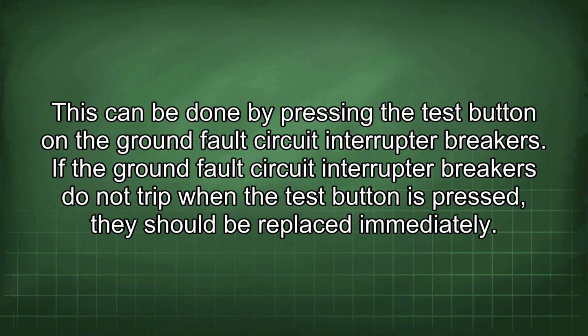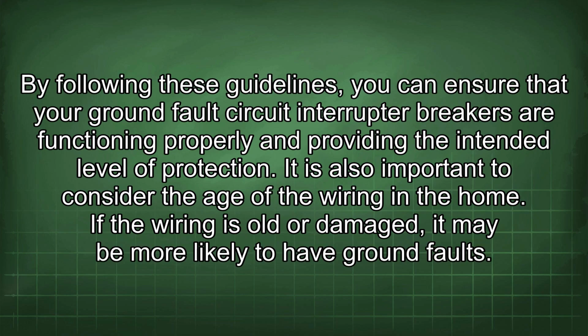If the ground fault circuit interrupter breakers do not trip when the test button is pressed, they should be replaced immediately. By following these guidelines, you can ensure that your ground fault circuit interrupter breakers are functioning properly and providing the intended level of protection.